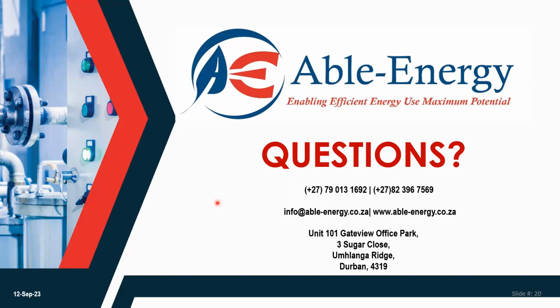And unfortunately I'm going to say something that will surprise a lot of people. You get standby generators with an automatic transfer switch, some of which are make-before-break, and some are break-before-make, and they have a big impact. So when your Eskom supply or municipal supply comes back, does that breaker and your PV synchronize with one another and then open? Or does it open and now you've got to bring a UPS in? So you've got to have a lot of operational experience and design - it's not only the energy mix, it's managing how that energy mix is taken on and off.